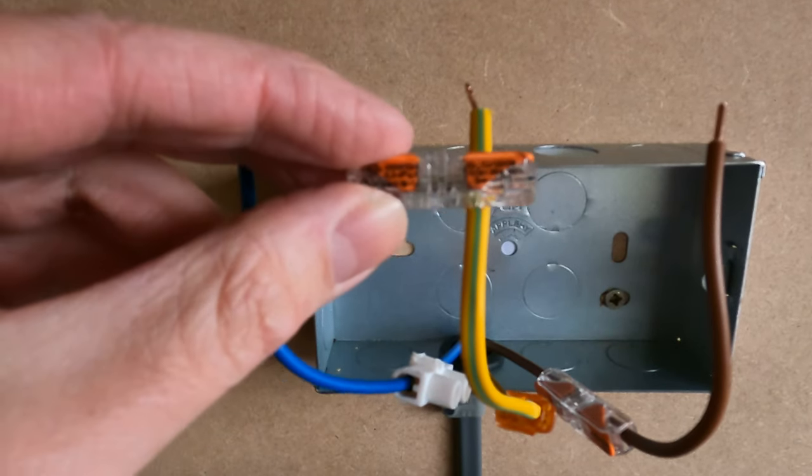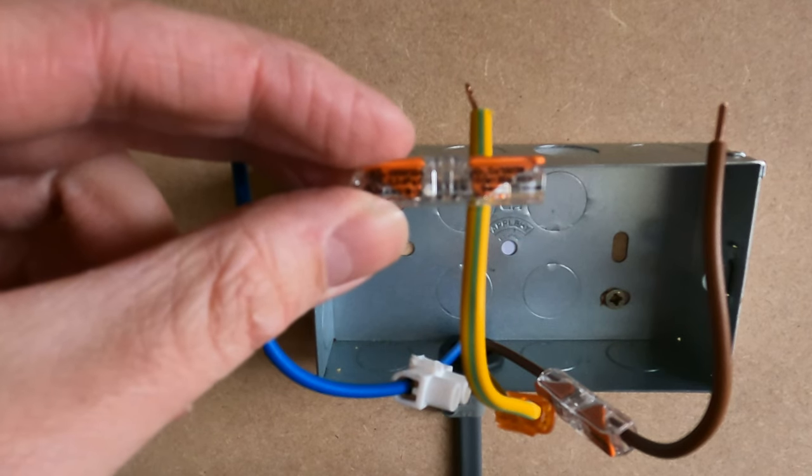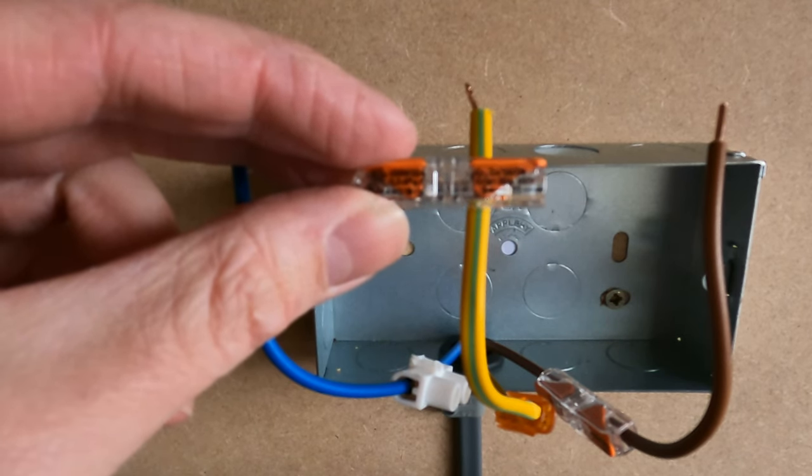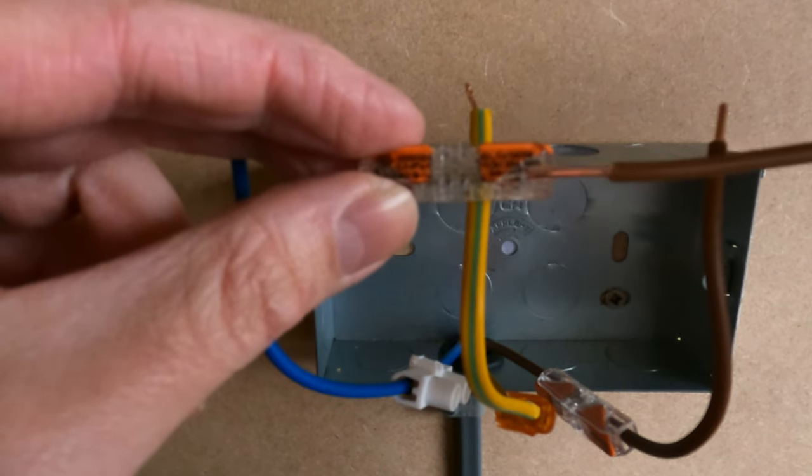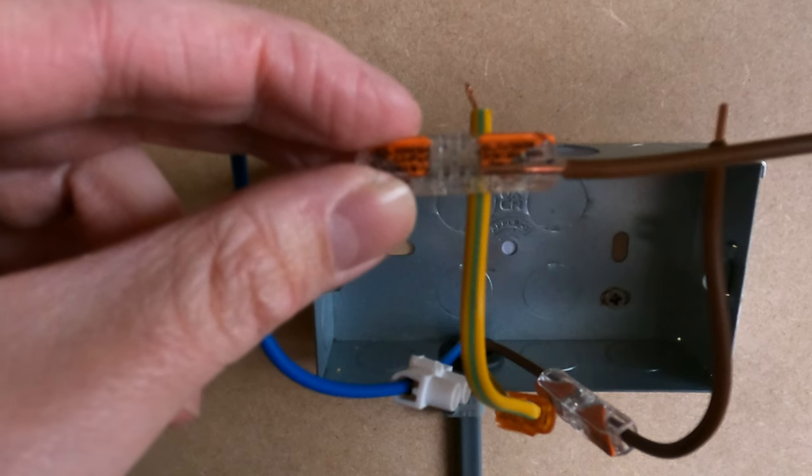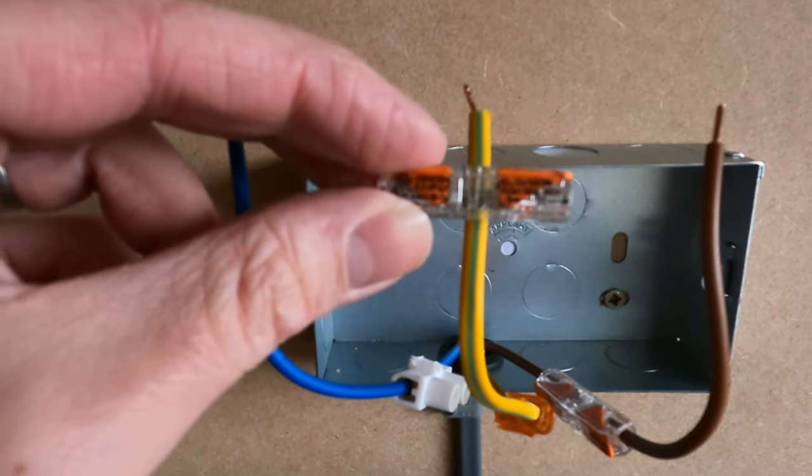So these are definitely my favorite way of connecting and extending wires. And these Wagos can accommodate a range of different sizes for your cable from 0.2 mil right the way up to 4 mil. And the other thing I like about it is there's a little diagram there where it shows you how much to strip off your cable, it's 11 mil, which is quite a handy little feature as well.